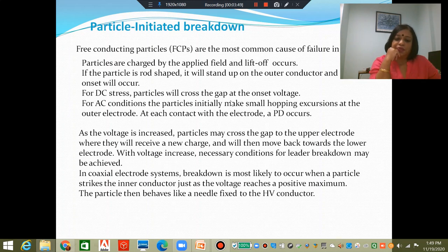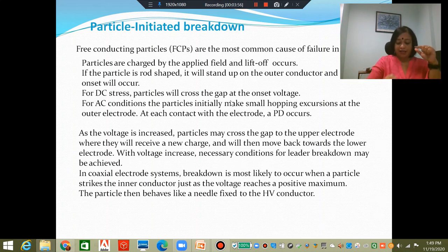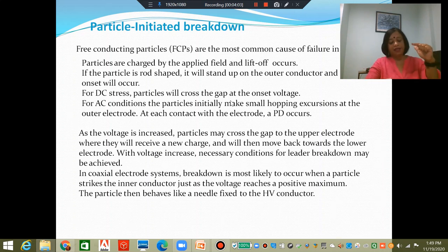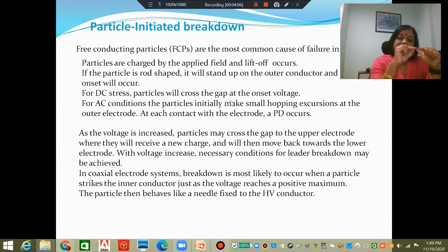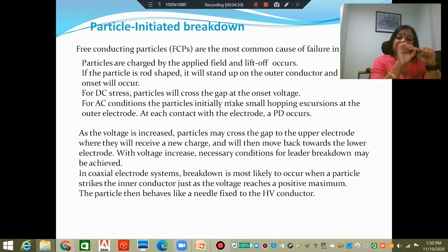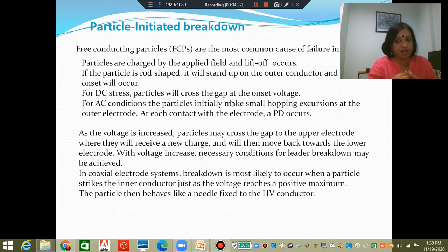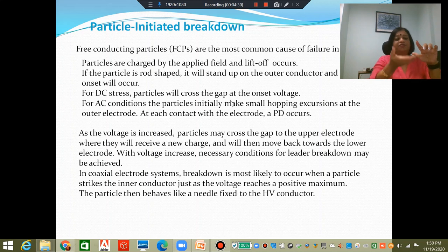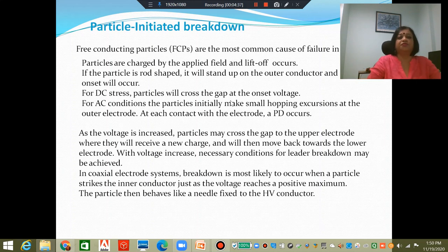In a coaxial electrode system, breakdown is most likely to occur when a particle strikes the inner conductor just as the voltage reaches a maximum. With AC, as voltage increases, the hopping excursions become longer and longer, and if the particle reaches the inner electrode at positive maximum potential, it is equivalent to the high voltage conductor having a protrusion. The same can happen with DC — as it lifts off, it can reach the inner conductor and behave as a protrusion of the high voltage conductor.